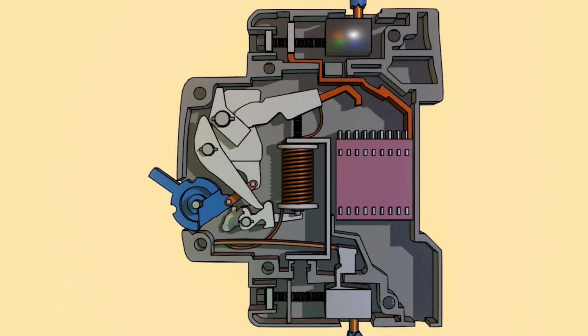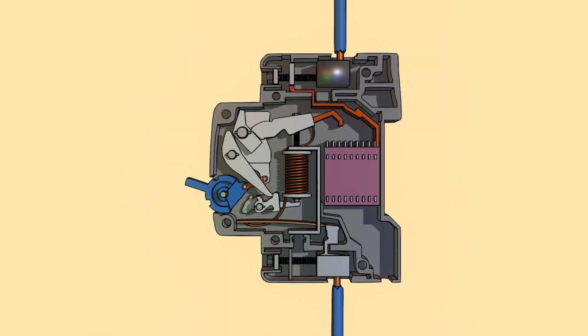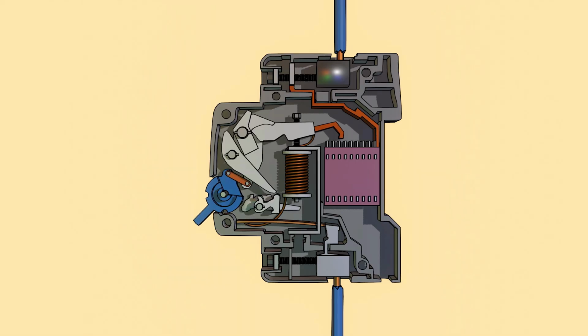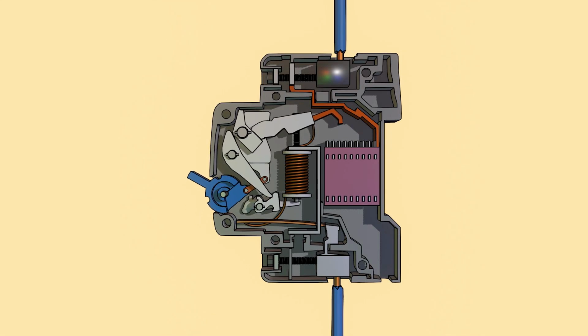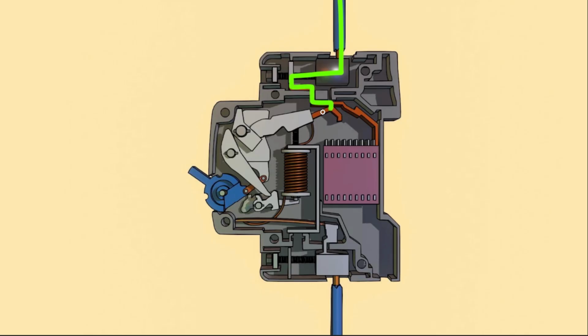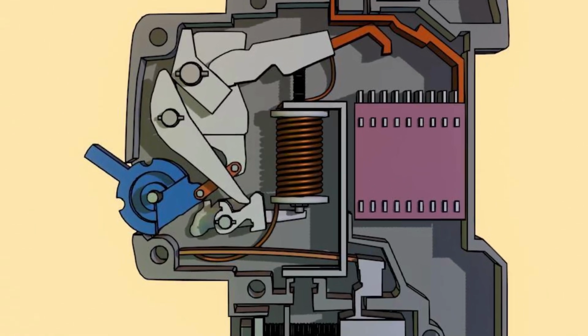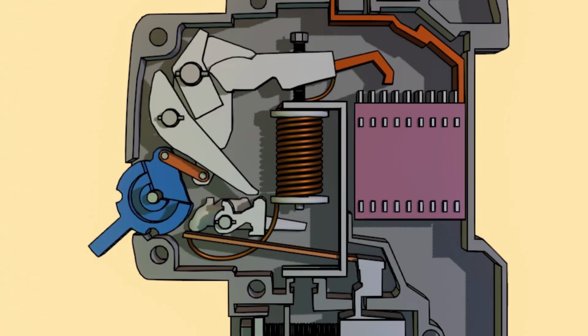Now suppose, for any reason, we want to switch off the circuit manually. We can do it by operating the handle. When we pull down the switch, it rotates. Accordingly, the moving contact detaches from the fixed contact, breaking the circuit. That is manual operation. Now, if there is an overloading condition, the current beyond the limit flows through this path and the bimetallic strip. Due to high current, the strip heats up and bends. It pushes this point, and as soon as it does, this spring-loaded lever is released. The mechanism rotates and the moving contact moves away from the fixed contact, breaking the circuit under overloading.